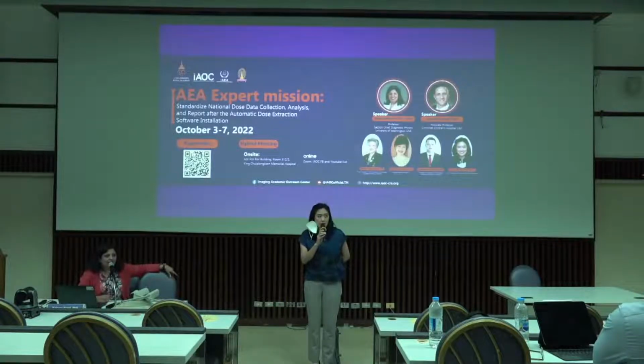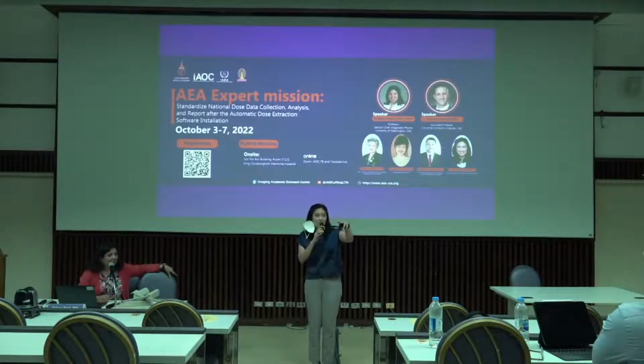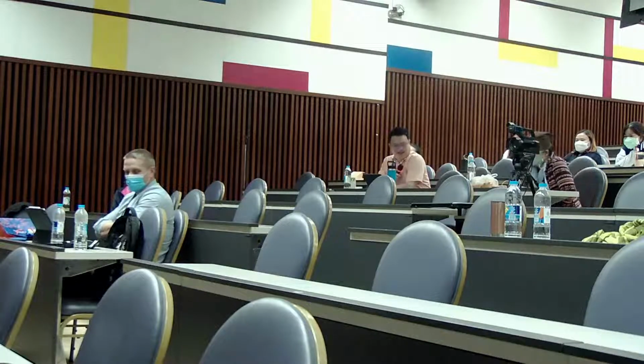Yeah, but I think what Tanya is asking about is on the scanner, what I showed you, the NV value. Normally whether you have it set up for your protocols. Yeah, they have it. I mean, every hospital with a new CT scanner has that dose alert level set, right? But that is maybe the first step, and then the second step is to email someone. No, that you need the dose management system. But a lot of the time technologists just click ignore. It's like MRI when you have the high SAR level, just ignore. Oh, how did you teach your students like that? No, because we can't proceed with the scan. Okay.